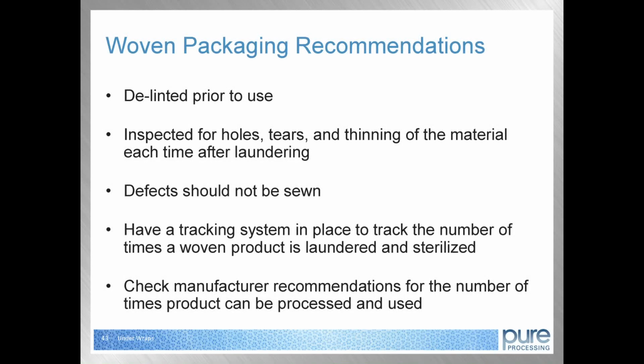Additionally, all woven packaging materials should be delinted prior to use. All woven packaging materials should be inspected for holes, tears, and thinning of the material each time after laundering. It is recommended the inspection take place with the use of a lighted table. Defects should be repaired with the use of a vulcanized patch that is heat sealed onto the woven material. A patch should be placed on each side of the defect. Defects should not be sewn.